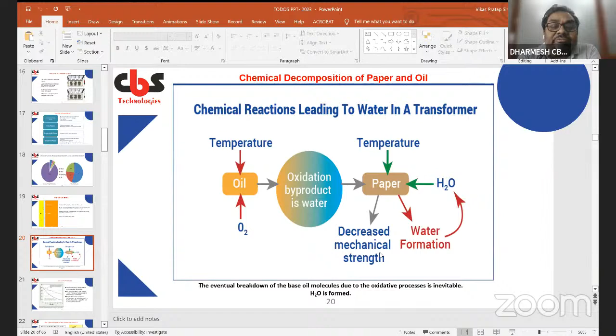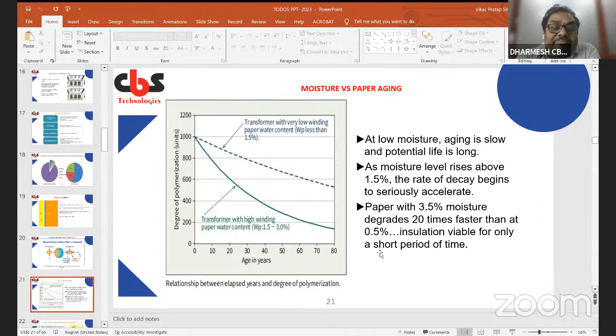Next, here you can see moisture versus paper, how the paper ages when moisture enters. At low moisture, aging is very slow and potential life is very long. But as moisture level rises to around 1.5%, the rate of decay begins to seriously accelerate. Paper with 3.5% moisture degrades 20 times faster than paper with 0.5% moisture, and such insulation is viable for only a short period of time.